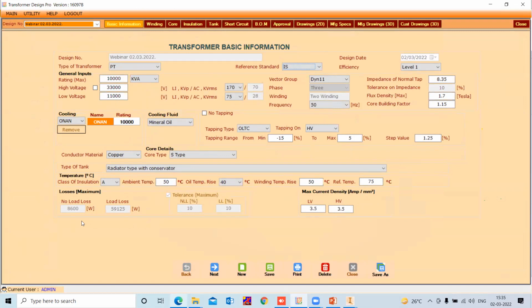Then the oil type. The other options are available to choose the cooling type. You can also see the lightning impulse and highest withstand voltage in kV RMS. So based on these impulse levels, your winding arrangement and insulation arrangement will change automatically. Vector groups, we have delta delta options, star star options, star delta option.